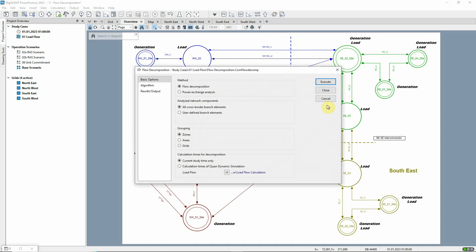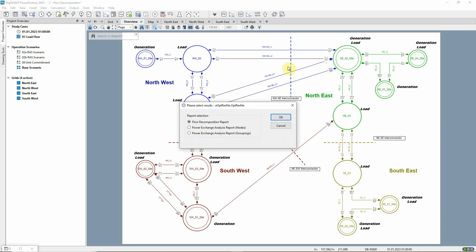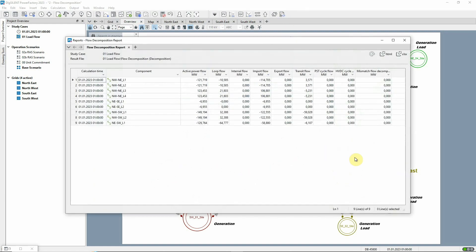Results from the flow decomposition command provide an overview of such unscheduled flows and will also identify HVDC and phase shifter cycle flows. This information can be used to determine the transfer capacity available for trading and provide assurance about expected circuit loadings.